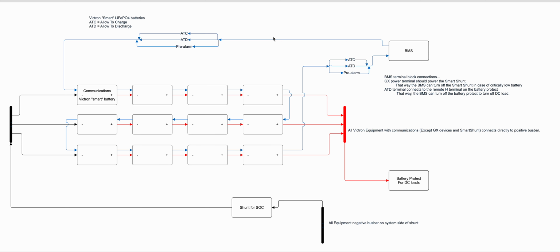Now the new NG series, the new generation series batteries, they use the same communication cable, but it's using a more complete communication protocol. It's not exactly published what they're using, but it might be something like CAN. So they're using the same cables, but then the BMS is actually receiving data like cell voltages and cell temperatures and all of that. But in this case, the BMS is only reading: is it okay to charge? Is it okay to discharge? And is there a pre-alarm? And so then the BMS handles all of that.